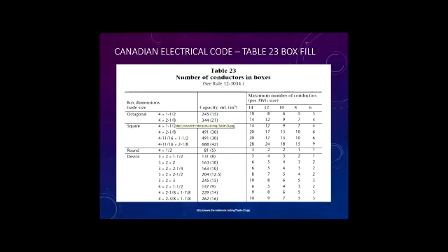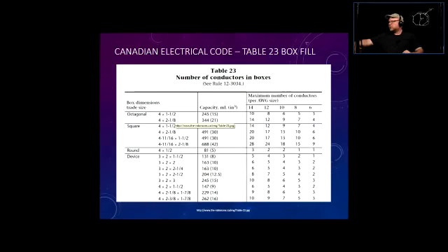All right, so the last number usually is going to show you the depth of the box. If you read the number from the last towards the front, the last number is going to give you the depth. So we have an octagonal box, 4 inches by 1.5 inches. Now it is calculated that the volume of that box is 245 milliliters, or 15 cubed inches. So that's the volume of it.